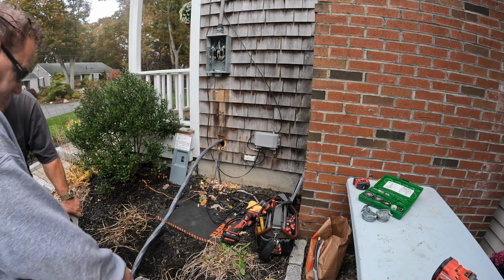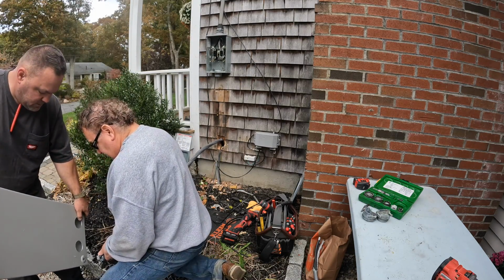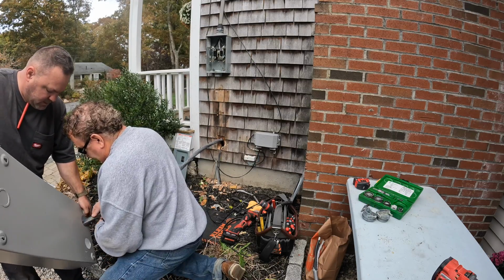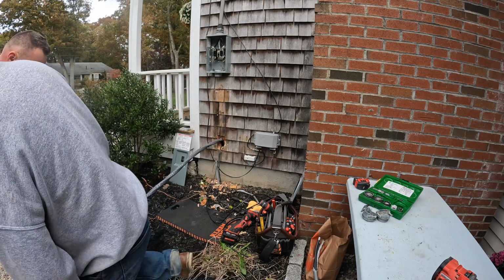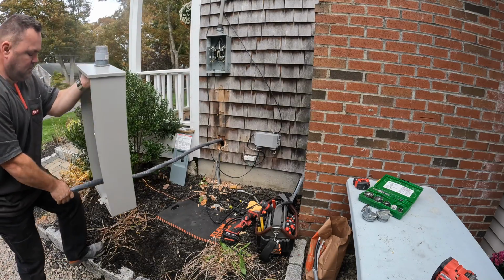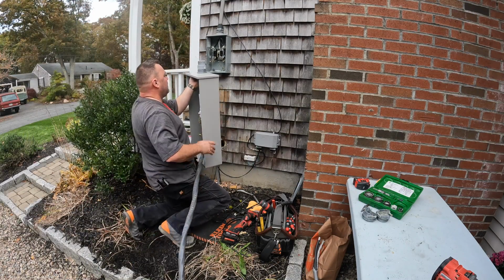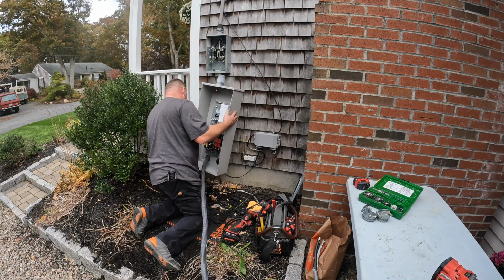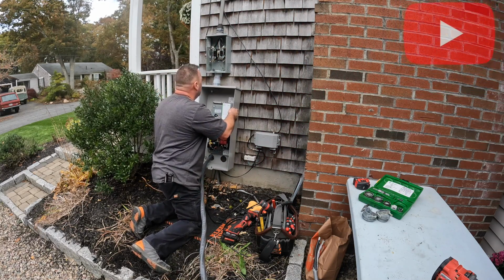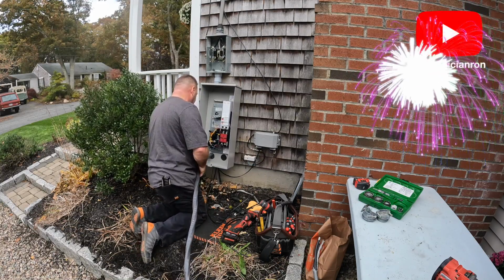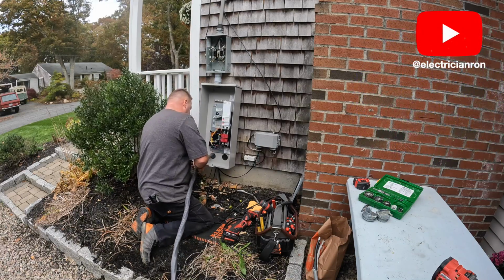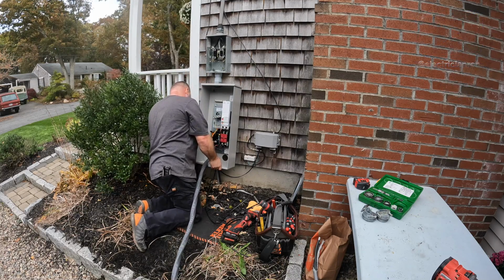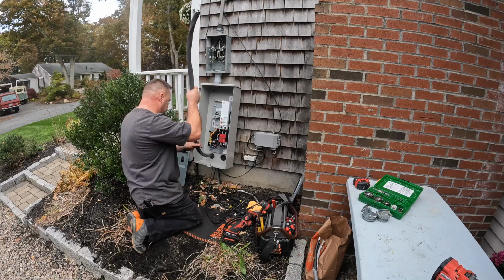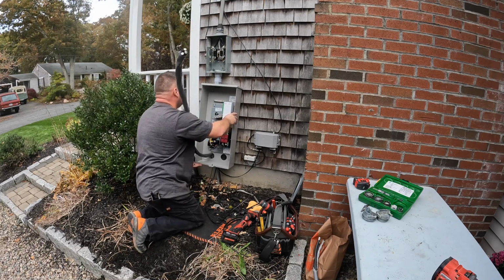Obviously there are a lot of ways to do this, and you could measure things and do approximations, but I like to get a nice dry fit. What I'm going to do is slide this enclosure up on the service entrance riser to the panel. The hole on the bottom right is where the generator cable is going to enter the transfer switch. Here I just want to get a dry fit, then mark the hole I made in the bottom right corner for the generator wire. Then I'll take it back off, make my permanent holes, and slide the generator cable into position.